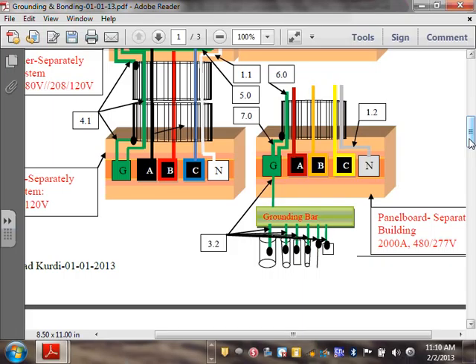The idea, guys, if you bond here, everybody knows why we don't bond. If you bond here, then your EMT conduit starts carrying neutral current. Under normal operating condition, your EMT conduit or rigid is carrying current. So it's good in Minnesota because it heats up and keeps warm, right? But the idea is it's a hazard, right? The hazard is now your conduits are carrying current under normal operating condition. Conduit shall not carry current except under abnormal condition. What's the abnormal condition? Ground faults. Ground faults. That's all. Now you could do that and bond in here and live with it forever, and nothing might happen.